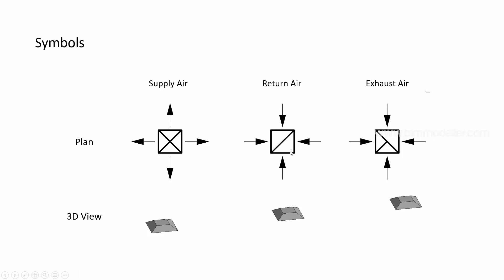If you see the difference in the middle: return air will always have a symbol like a square or rectangle shape with a diagonal line. Exhaust has an additional line connecting the diagonal line. For supply, it will be a cross line. You have to remember these shapes and arrow directions. In 3D, all look similar — it will be based on the family created in the project.